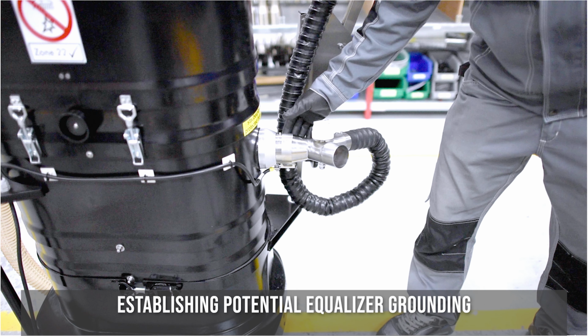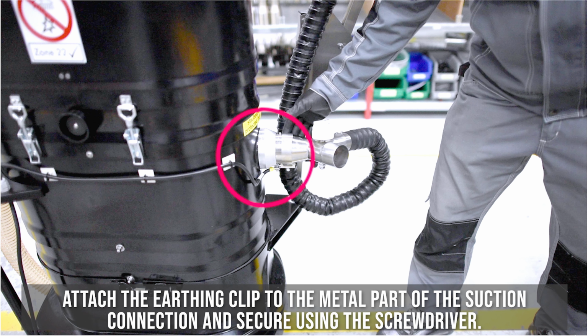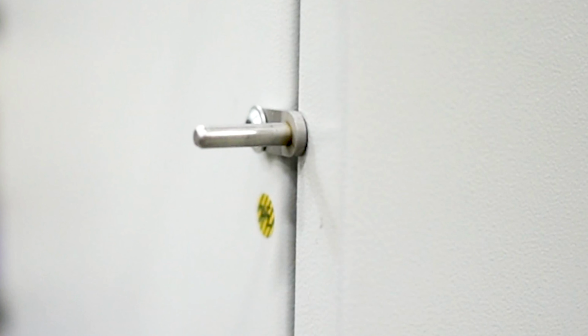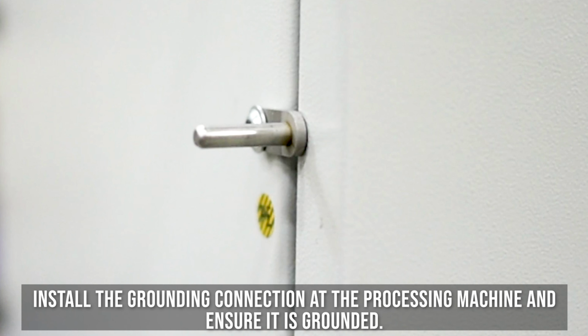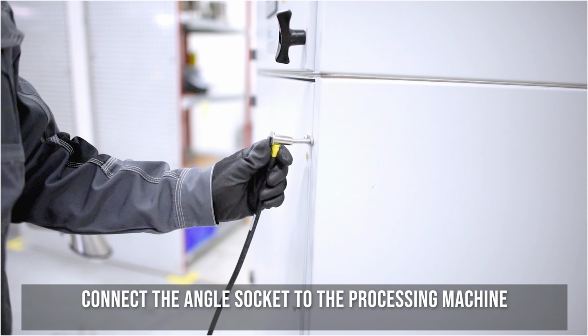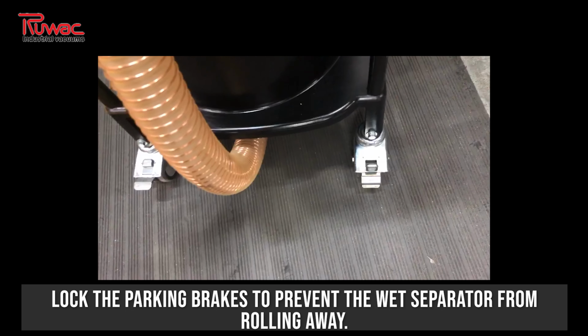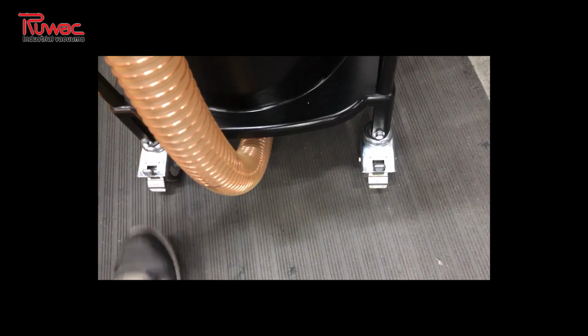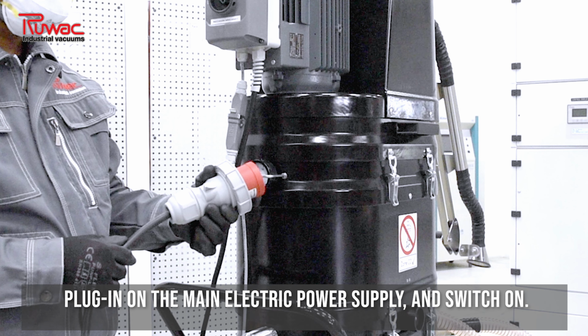NA35D1 commissioning. Establishing potential equalizer grounding. Attach the earthing clip to the metal part of the suction connection and secure it using the screwdriver. Install the grounding connection at the processing machine and ensure it is grounded. Connect the angle socket to the processing machine. Lock the parking brakes to prevent the wet separator from rolling away. Plug in the main electric power supply and switch on.